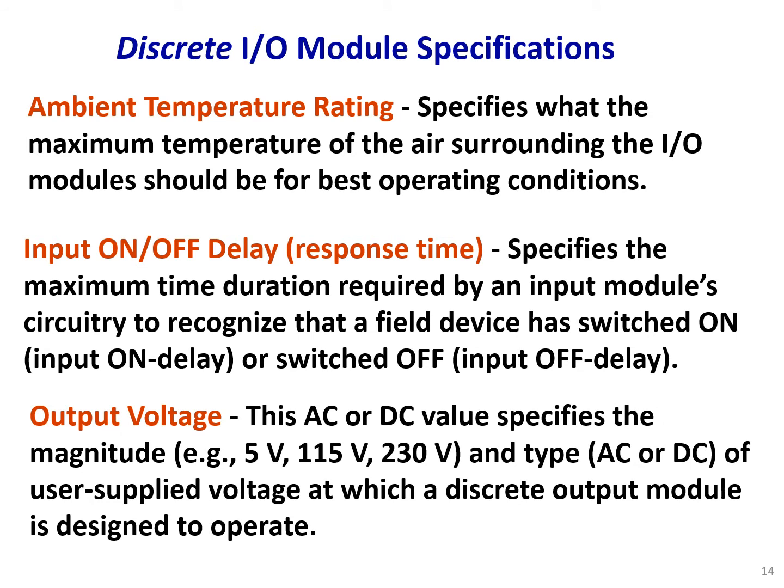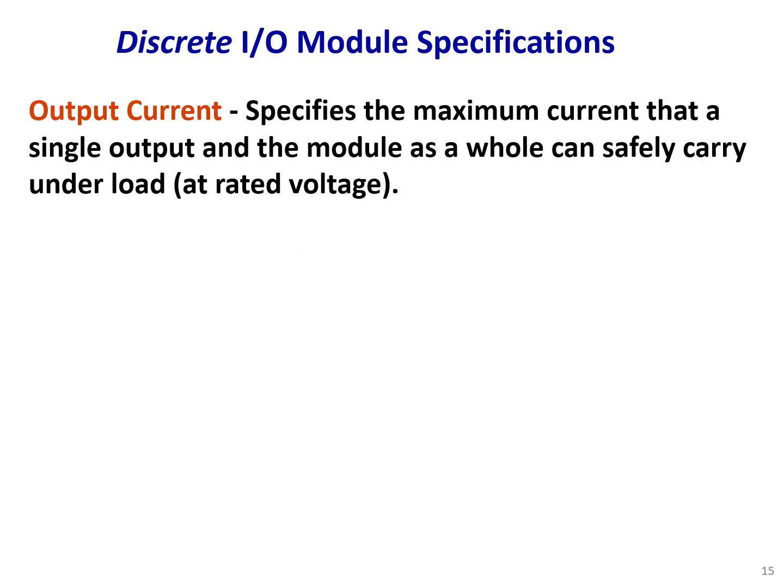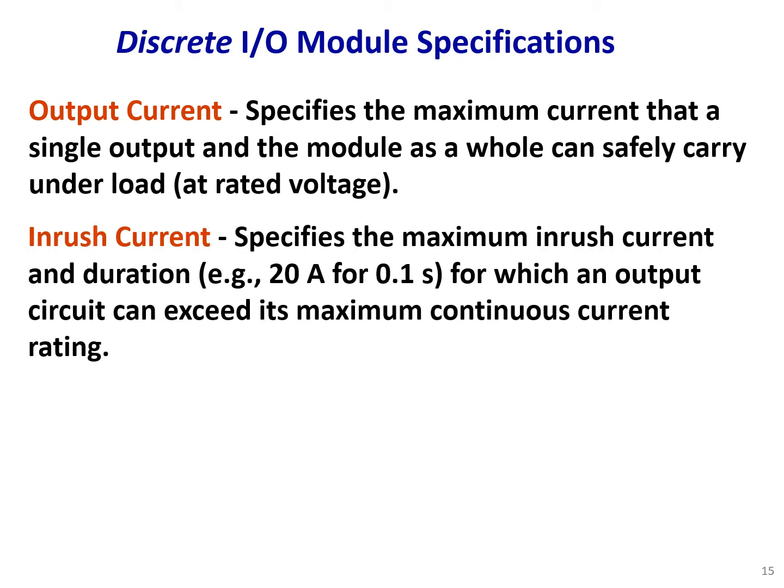The output voltage — AC or DC — specifies the magnitude, for example 5, 115, or 230 volts, and type of user supply voltage at which a discrete output module is designed to operate. Output current specifies the maximum current that a single output and the module as a whole can safely carry under load. Inrush current specifies the maximum inrush current and duration — for example, 20 amperes for 0.1 seconds — for which an output circuit can exceed its maximum continuous current rating.